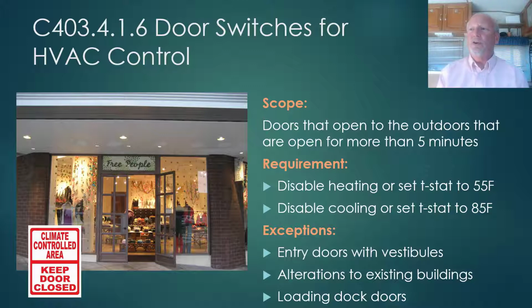And so there is a new control provision for doors that open directly from a conditioned space to the outdoors. If the doors are open for more than 5 minutes, there shall be a control that will disable the heating or set the thermostat to 55 degrees or lock it out. So no heating or reduce the set point. And the same thing on the cooling side, either disable the cooling or increase the set point to 85 degrees Fahrenheit. Hopefully this will reduce the energy loss going out through the door.